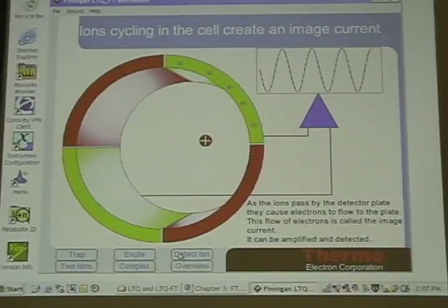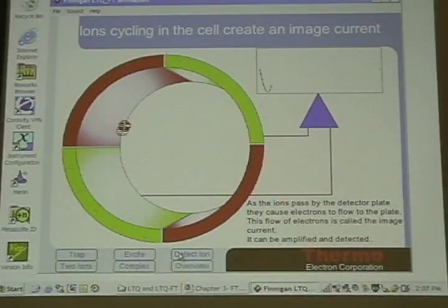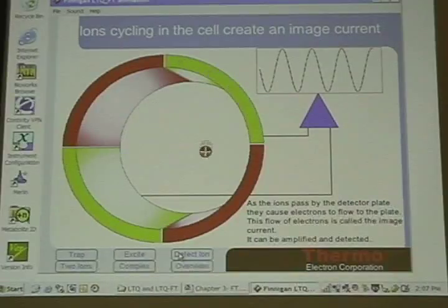We take this signal, we Fourier transform it, and we get out the frequency of motion. We then take our calibration equation, okay, which we did during our mass calibration. So now here's my second Fourier transform calibration, which is also divided into 6 parts. 3 positive, 3 negative across each mass range. Okay, so there's 6 excite calibrations. Now there's 6 mass calibrations. Okay, you guys with me?